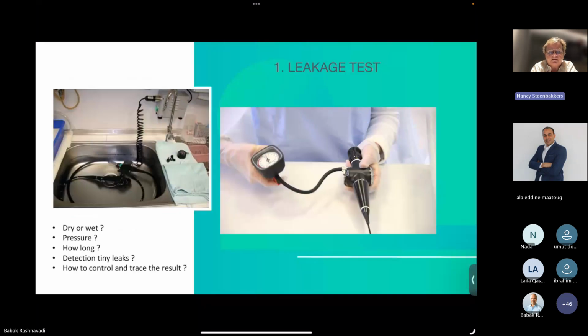Then you have to rinse all the channels. If you forget to rinse one channel with water and detergent, you will not clean and you will not destroy any biofilm. And after the rinsing of all the channels, then you have to brush, and then you have the after rinsing. So here, this is just an example of how we see that people are doing it in endoscopy departments. So they do it either on the right side manually, which is very good in a dry way. But of course, you have to use one operator to perform the leak test, and at the same time they cannot do anything else. On the left side, you have this Olympus pump, which is a good pump, but it's not smart enough to give an idea if there is a leakage or not, because there is no sign on it. So you really have to soak it underwater to see visually if there is a leakage or not. So I try to avoid all kinds of human actions to avoid these kinds of mistakes.